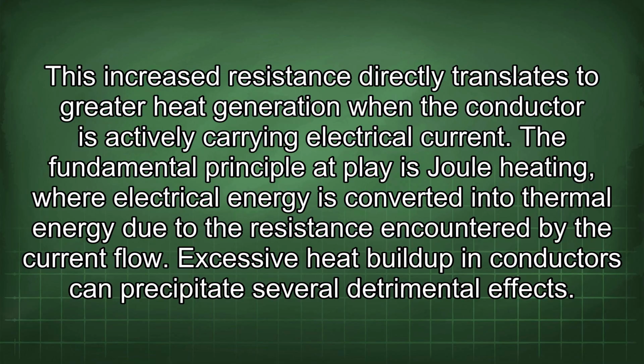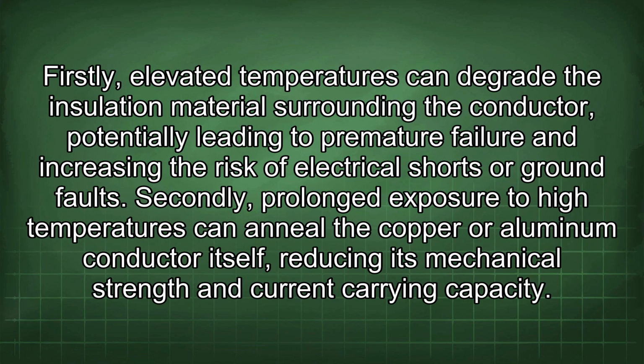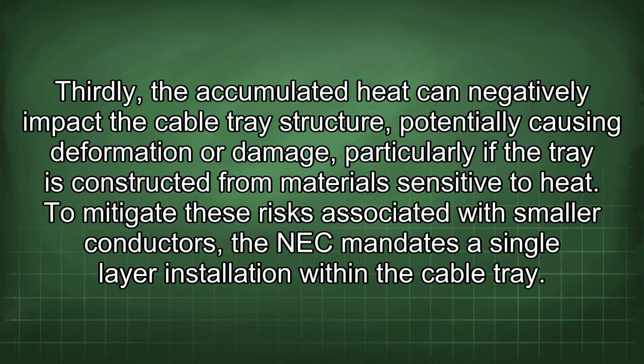The fundamental principle at play is Joule heating, where electrical energy is converted into thermal energy due to the resistance encountered by the current flow. Excessive heat buildup in conductors can precipitate several detrimental effects. Firstly, elevated temperatures can degrade the insulation material surrounding the conductor, potentially leading to premature failure and increasing the risk of electrical shorts or ground faults. Secondly, prolonged exposure to high temperatures can anneal the copper or aluminum conductor itself, reducing its mechanical strength and current carrying capacity. Thirdly, the accumulated heat can negatively impact the cable tray structure, potentially causing deformation or damage, particularly if the tray is constructed from materials sensitive to heat.